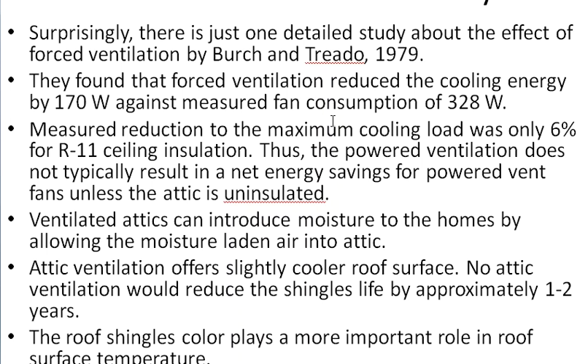However, the consumption of the fan itself was about 328 watts, so the consumption was higher than the saving. Also, the measured reduction to maximum cooling loads was only six percent for R-11 ceiling insulation. Overall, powered ventilation does not typically result in a net energy saving — the cost is more than the saving for powered fans, unless the attic is uninsulated, in which case it may provide some cost saving.